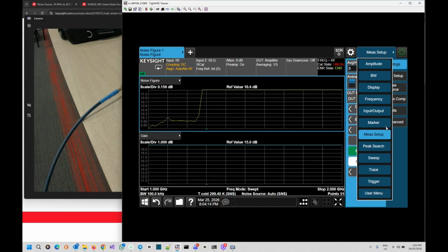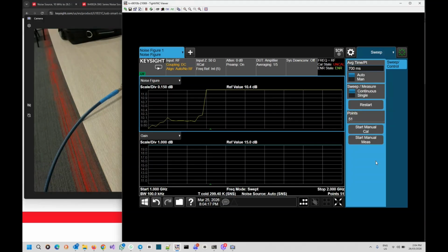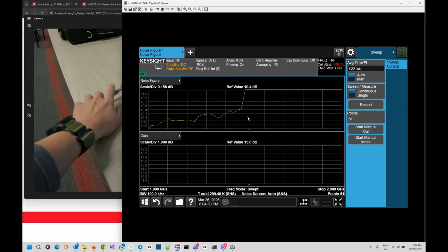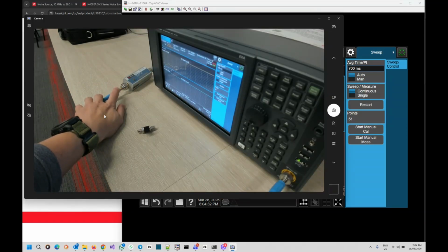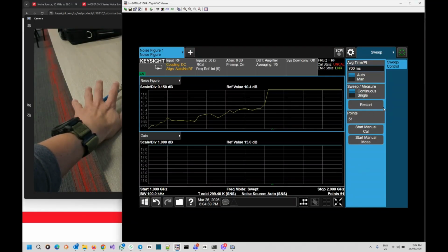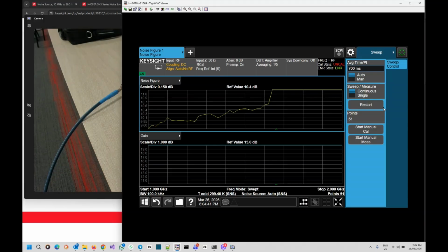One more thing to be aware of, once you have done the calibrations, this restart is very crucial, because when you have averaging on, the measurements will take the previous and the current and average them out. And if something changes on the connections while the measurement is still ongoing, it does affect the end result. So this is where you need to restart the measurements again.